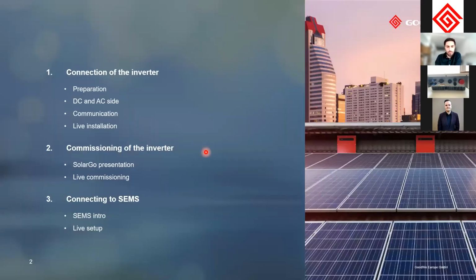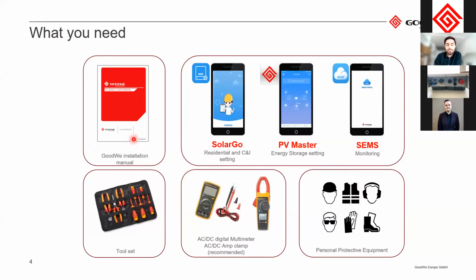The content for today is, first, the connection of the inverter and what you need to know there, then commissioning, and then the connection to SEMS. First off is the preparation before installing it. You will need the GoodWe installation manual. In there you will find everything necessary to install the inverter, such as the exact cable size, so please have an extra look in the manual if you have any questions. You will also need a basic tool set and a multimeter, and we recommend one with an amp clamp so you can measure the current. Please also have the correct protective equipment with you so that everything goes well.